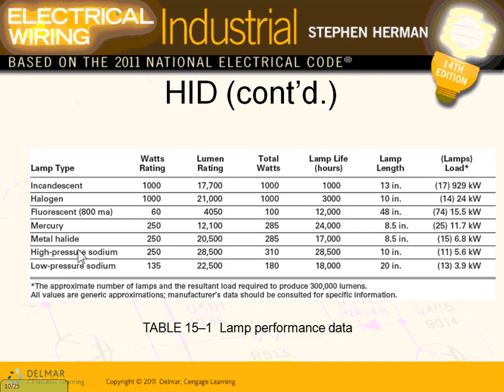Here's a nice comparison between fixture types. If you look at the LEDs, I like this because it covers all these types — based on the watt, the lumen, the total watts, as well as the lamp life. Lamp life is a big deal for maintenance. Looking at this, it tells you the incandescent lamp is the worst in terms of maintenance, whereas high pressure sodium is the best because it lives longer. By looking at one sheet like this, it gives you an idea of which one is best in terms of life expectancy.